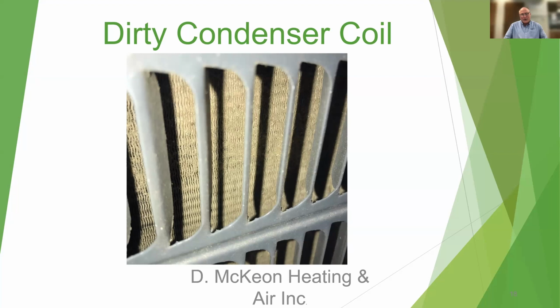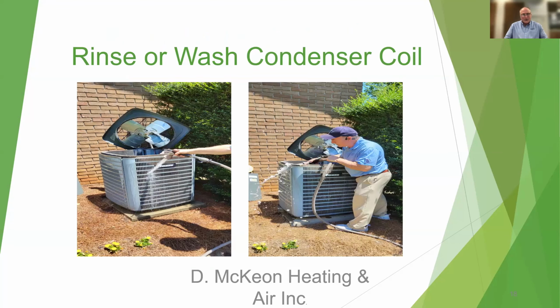So the photo on the left shows washing or rinsing the coil through the actual vanes of the outside grill of the unit itself. That's one way to do it, and if that's all you can do, then you do that. You would go up and down slowly, then push at an angle, which you can see the water is doing there.